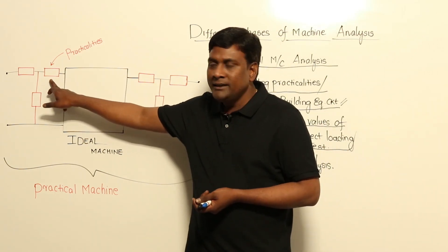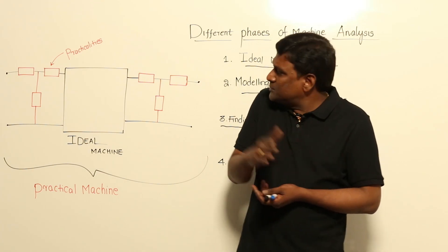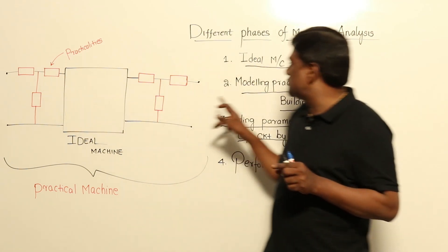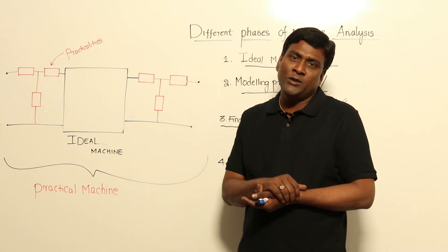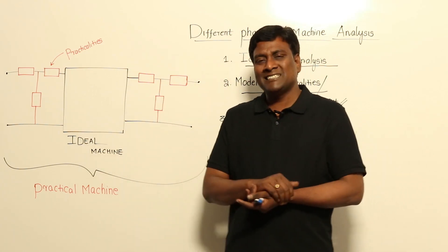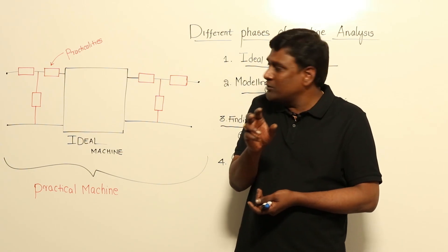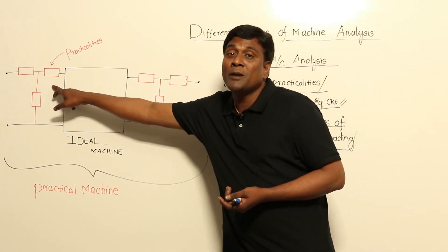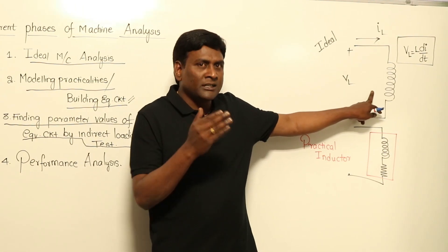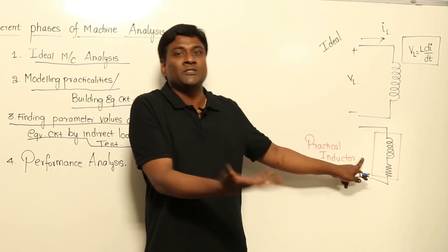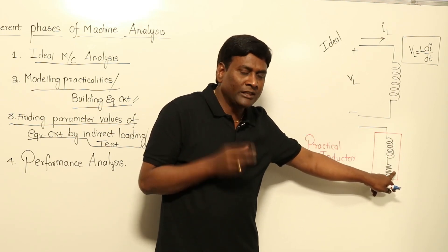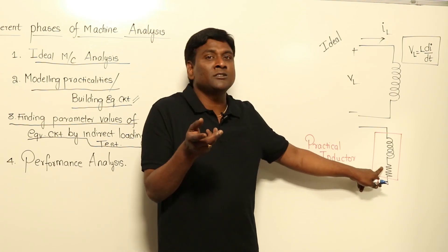For example, copper loss has been modeled as resistance — that is Phase 2. Now, finding how much is the value of that resistance is Phase 3. If a practical machine absorbs X watts as copper loss, I should model the resistance for those X watts. By indirect testing, I find the parameter values — how much is the resistance, how much is the inductance. That is Phase 3.